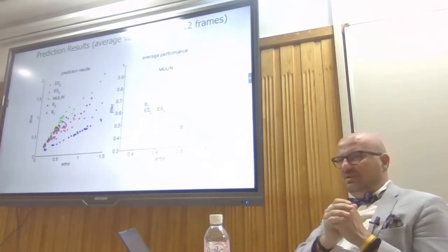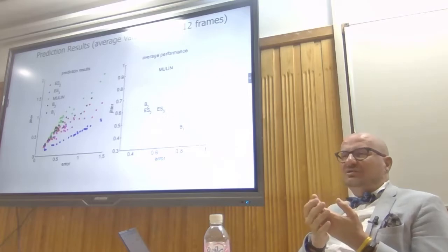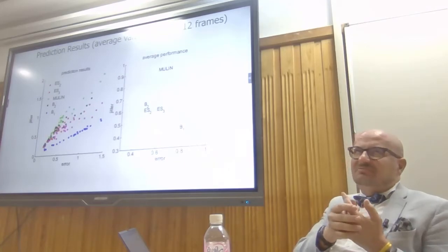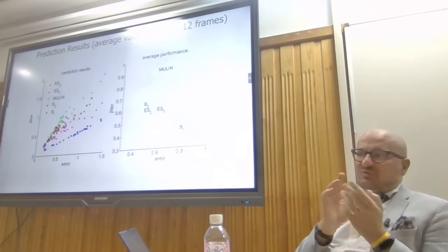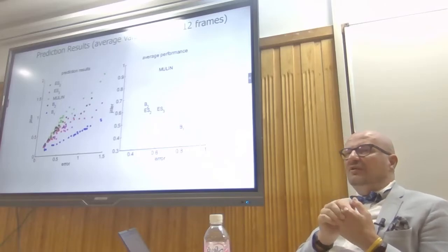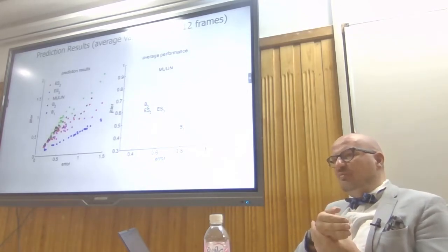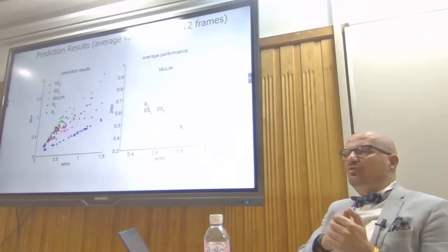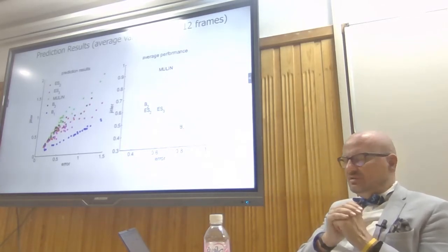Then again, you make several steps, you do calculations. If the patient's respiration is very periodic, very clean, then ES3 is the best model. It follows very well. If the patient's breathing is more hectic, or at some moment it becomes more hectic, you can switch to ES2, or even to B2, which is just an average that you follow stepwise.